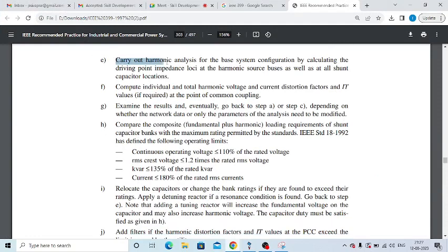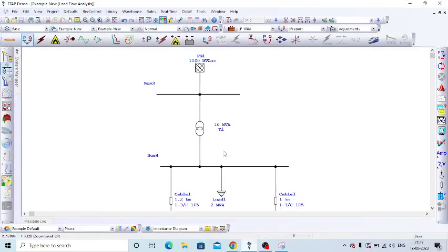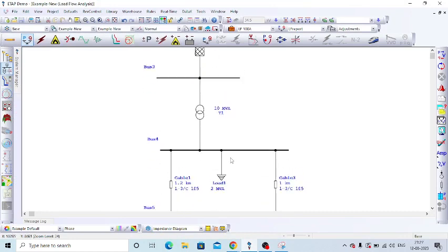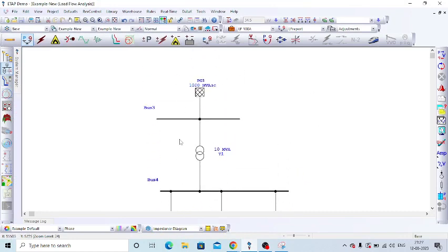Then carry out the harmonic analysis for the base system configuration. Base system configuration means, here it is a simple system, so only one configuration. In a large system, two power grid sources will be there, multiple transformers will be there, multiple generators will be there, and as we saw in the last session, a bus coupler or tie breaker. So switching the tie breaker on, switching the tie breaker off, like that we have to do the harmonic analysis multiple times.